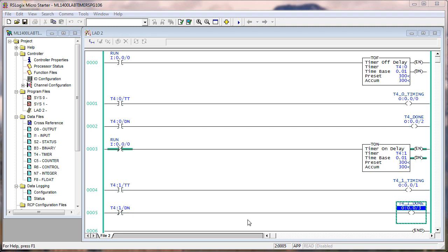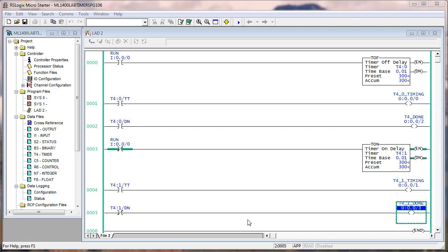So actually, rung 2 and rung 5 are the main players here. We're comparing the output devices connected to output colon 0.0 slash 2 and slash 3 to see how they compare. And the operation is identical. If I turn it on, they both go on. See, 2 and 3, outputs 2 and 3, they're on, right? And they stay on, as long as input 0 is on, they just stay on. When I flip it off, the timer time bit comes on, but the outputs 2 and 3, they go off together when the timers have accumulated to the point where the cum equals the preset.